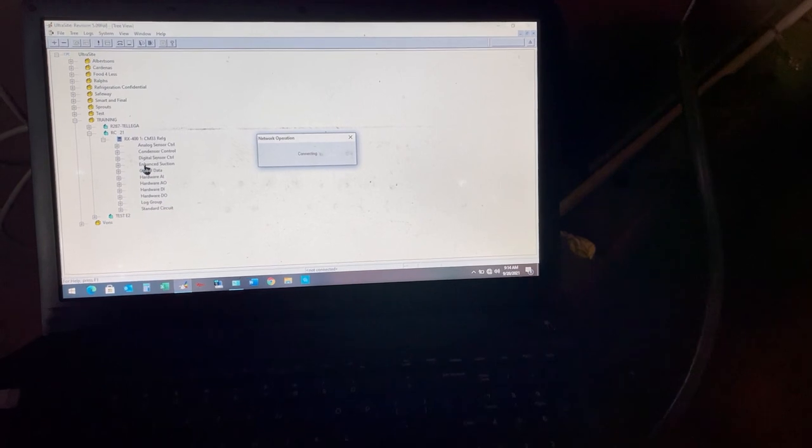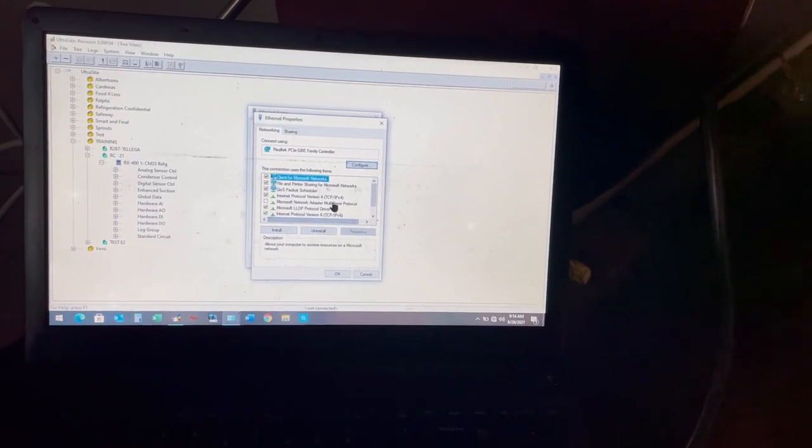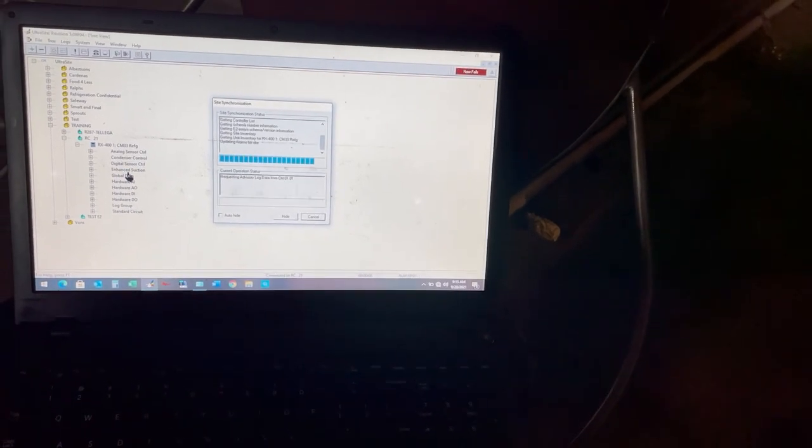And there you go. So I wanna go back to it and fix it. Gonna put in an IP that does not conflict with the controller. So going back to 13. In this case, 13 or 11 would work. Okay, close it. Try again. Right click, connect. And there you go. Now connected to the controller. Easy as that. That's how you connect to an E2 using your laptop.